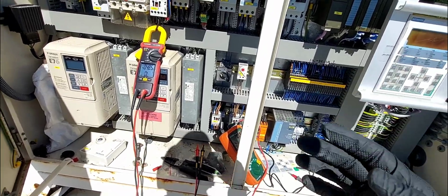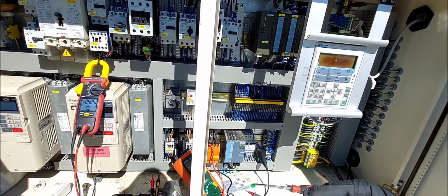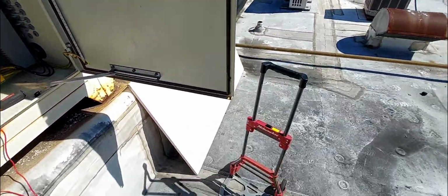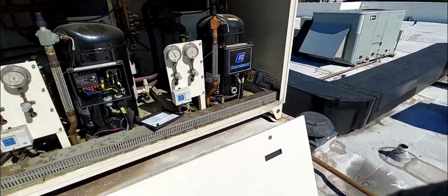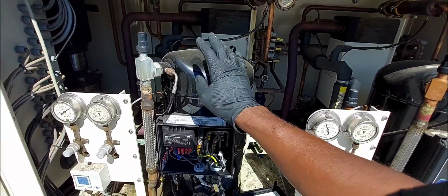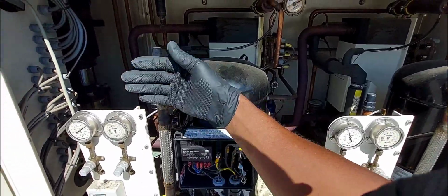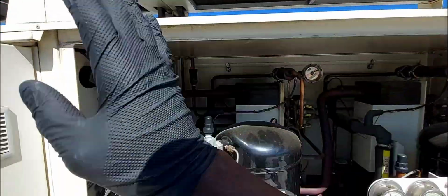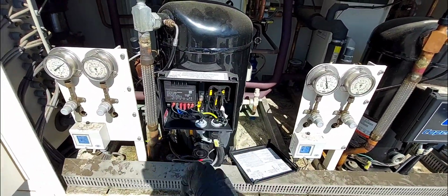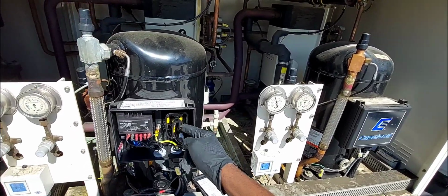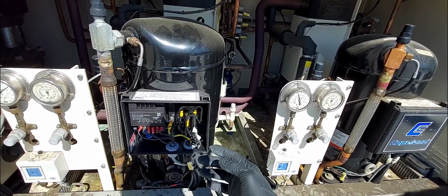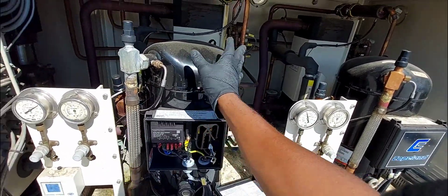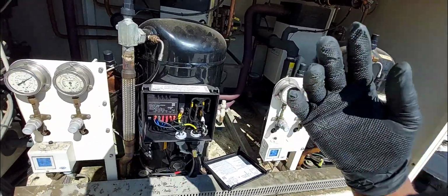So when you're Megger testing, what you're actually doing is testing the integrity, or the resistance value, of your compressor's internal windings to the chassis ground, or the casing of the compressor. And like I said, the casing of the compressor is connected to the pipe, which is connected to all the copper, to all the metal casing. It's all connected, and this is all grounded. Especially when it's a 460 compressor, high voltage, these things are notorious: if you have a slight leakage to the ground, it will trip. It will blow your fuse.